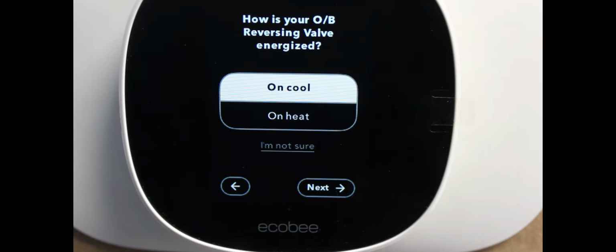How's your reversing valve energized? Everything that we install is going to be on cooling. Some of the equipment that we service might be on heat, so it's important to pay attention. The only brands that do switch in heating mode are going to be Rheem, Ruud, and Bosch.